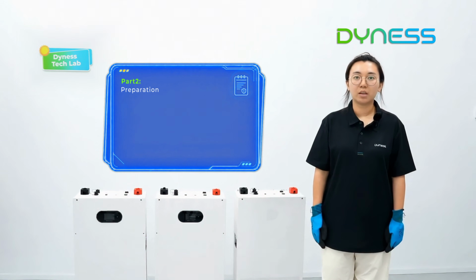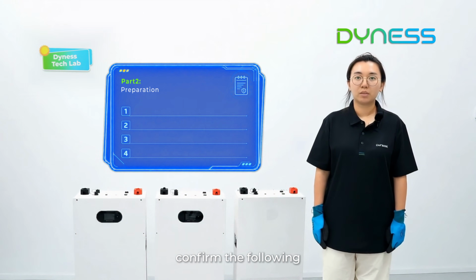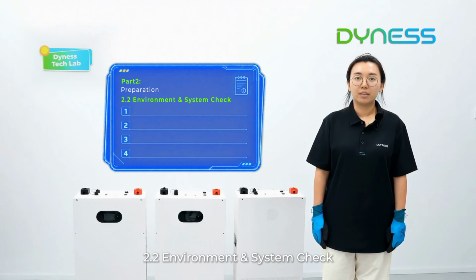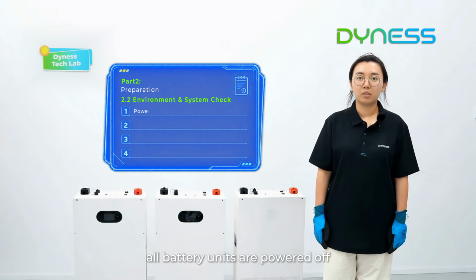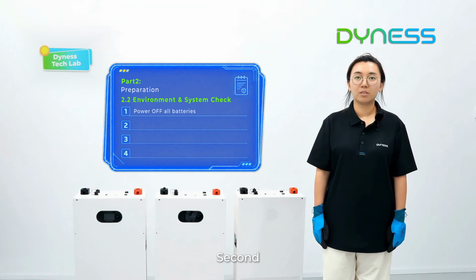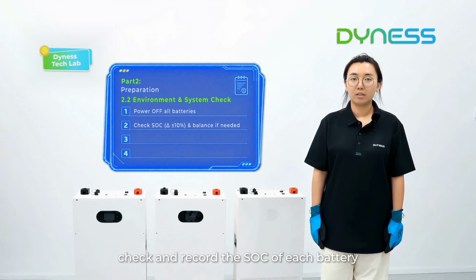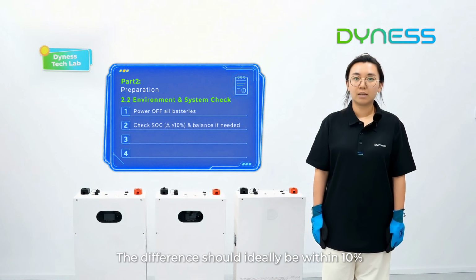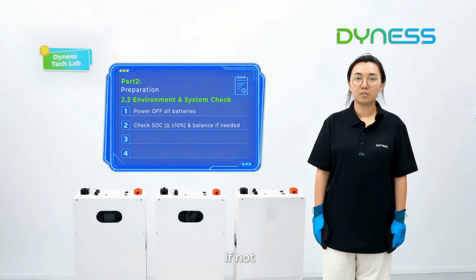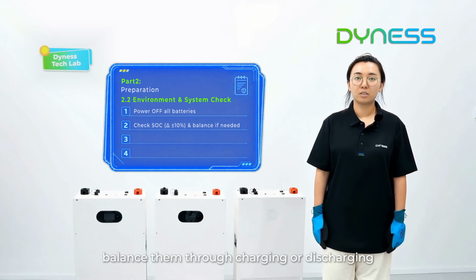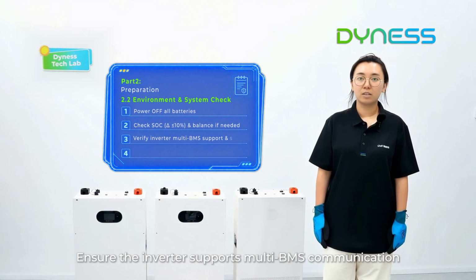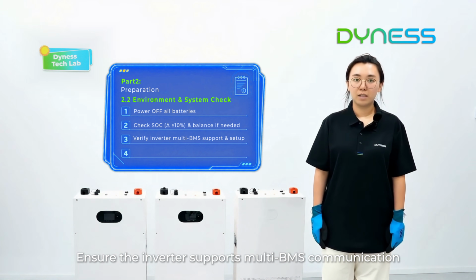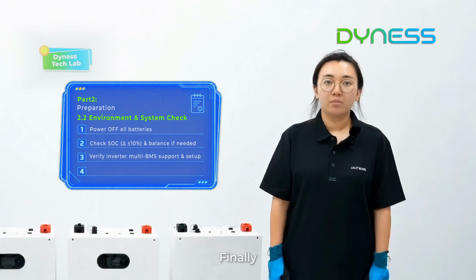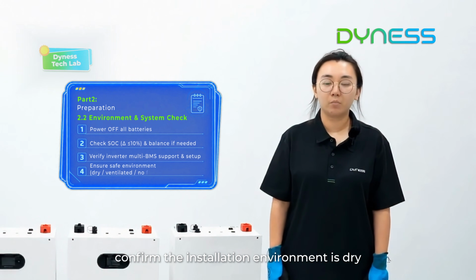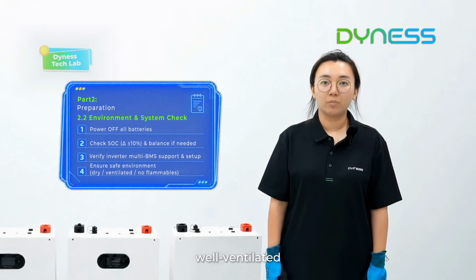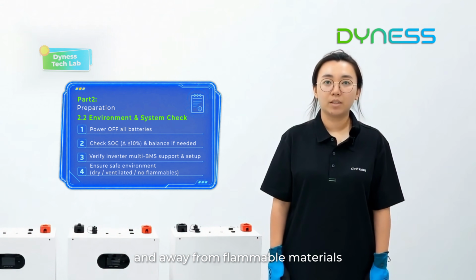Environment and system check. Before starting, confirm the following. 2.2 Environment and system check. First, all battery units are powered off. Second, check and record the SOC of each battery. The difference should ideally be within 10%. If not, balance them through charging or discharging. Third, ensure the inverter supports multi-BMS communication and is properly configured. Finally, confirm the installation environment is dry, well ventilated, and away from flammable materials.